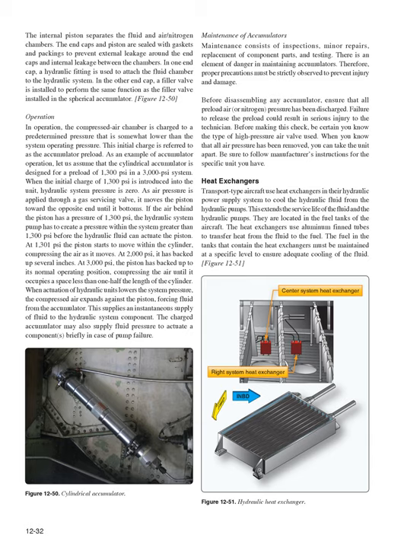As air pressure is applied through a gas servicing valve, it moves the piston toward the opposite end until it bottoms. If the air behind the piston has a pressure of 1,300 pounds per square inch, the hydraulic system pump has to create a pressure within the system greater than 1,300 pounds per square inch before the hydraulic fluid can actuate the piston. At 1,301 pounds per square inch, the piston starts to move within the cylinder, compressing the air as it moves. At 2,000 pounds per square inch, it has backed up several inches. At 3,000 pounds per square inch, the piston has backed up to its normal operating position, compressing the air until it occupies a space less than one-half the length of the cylinder.